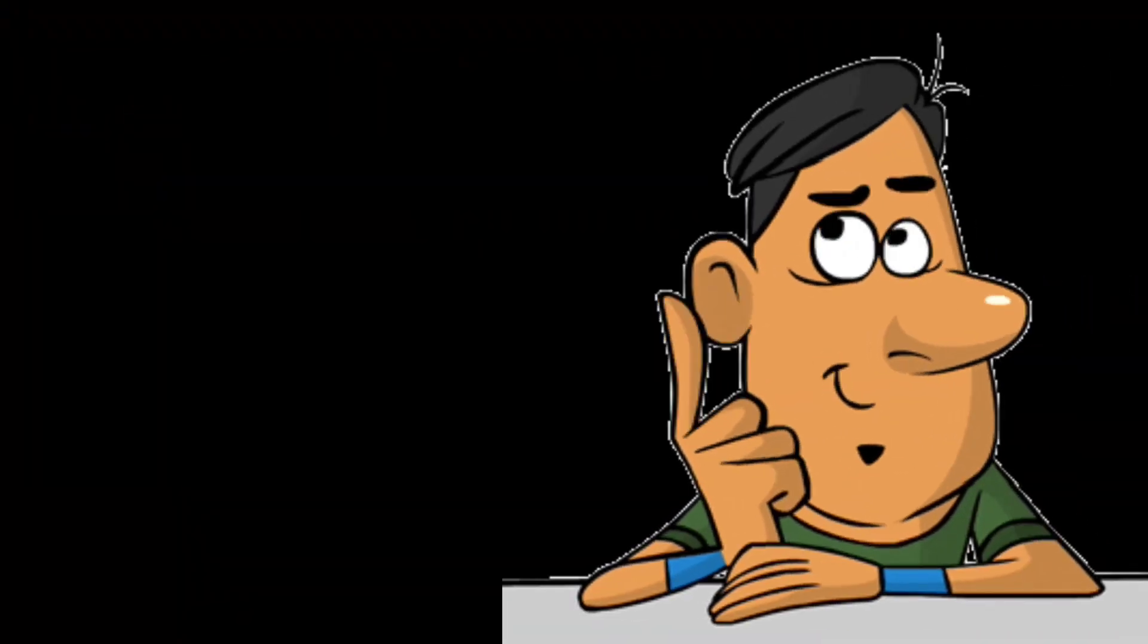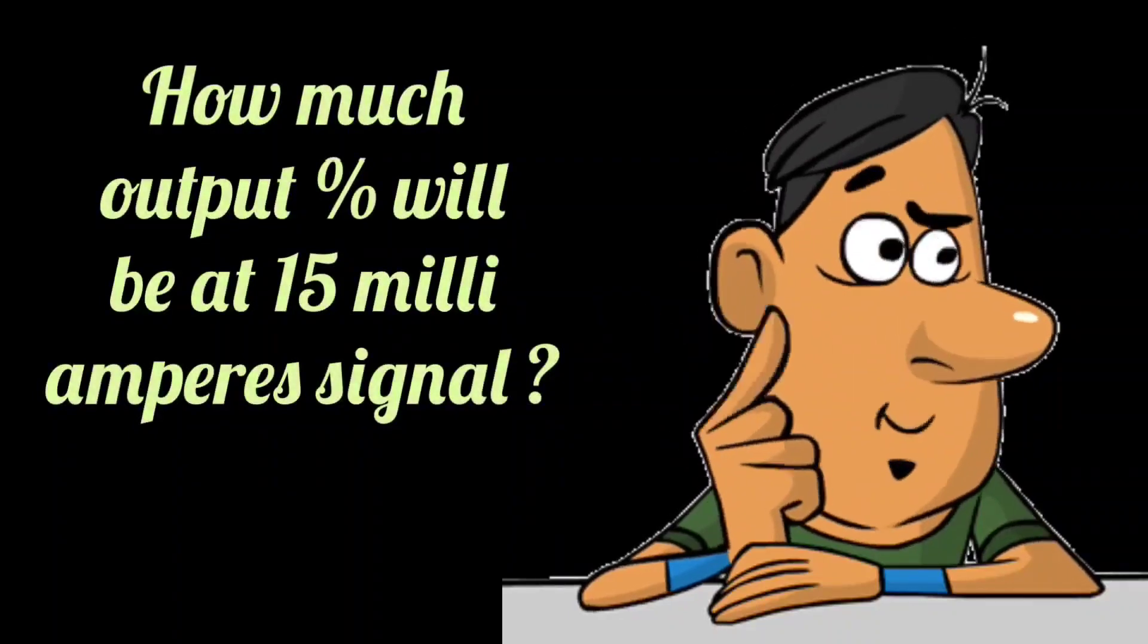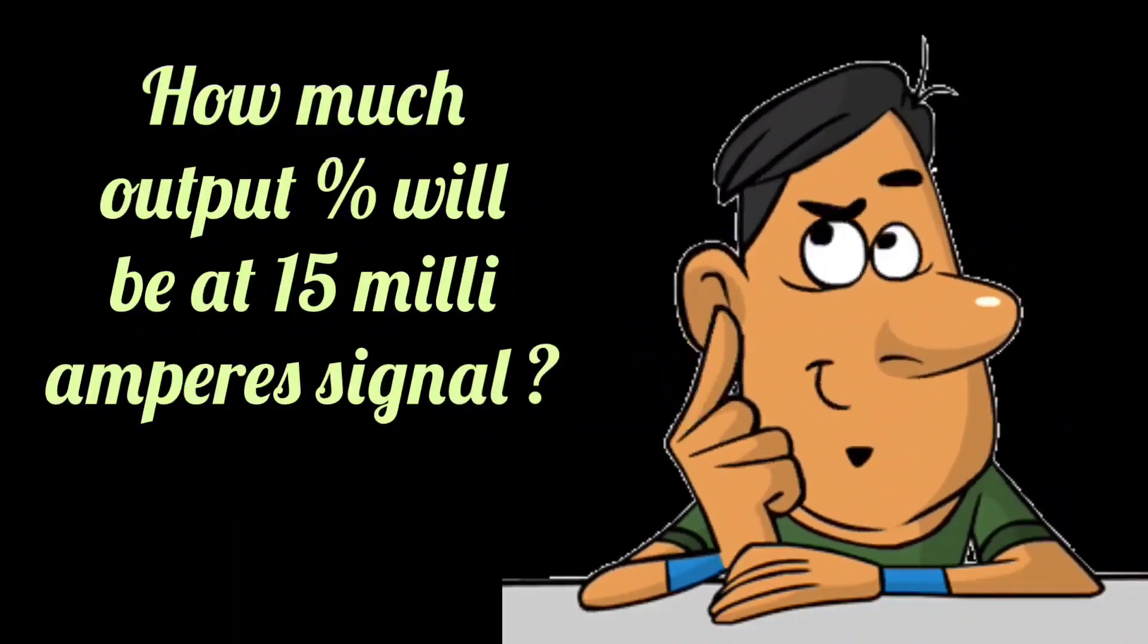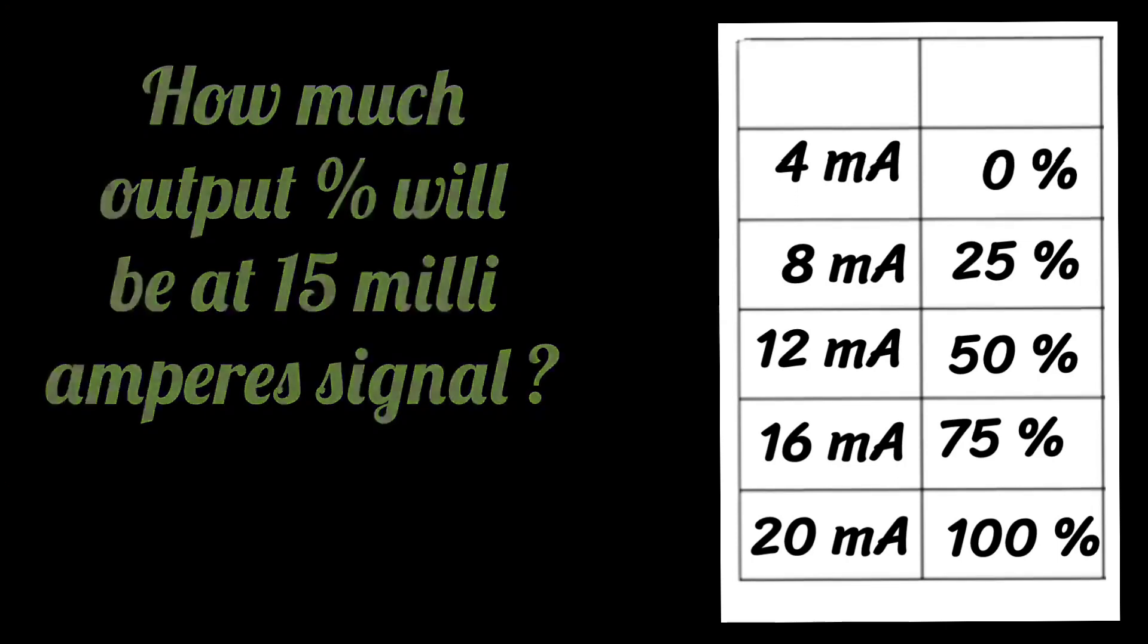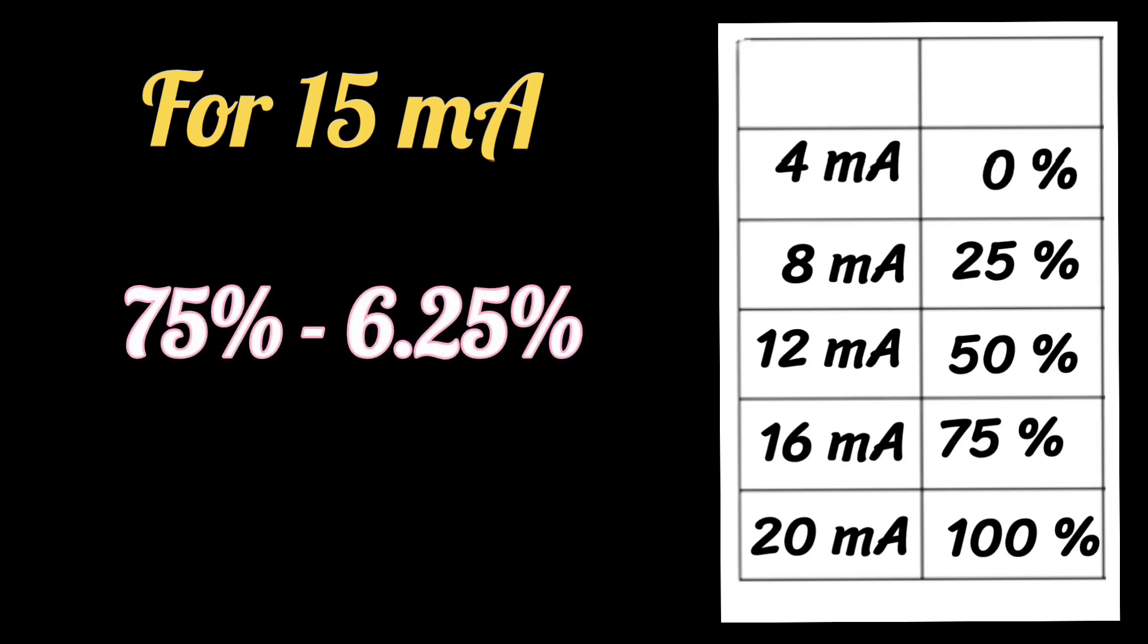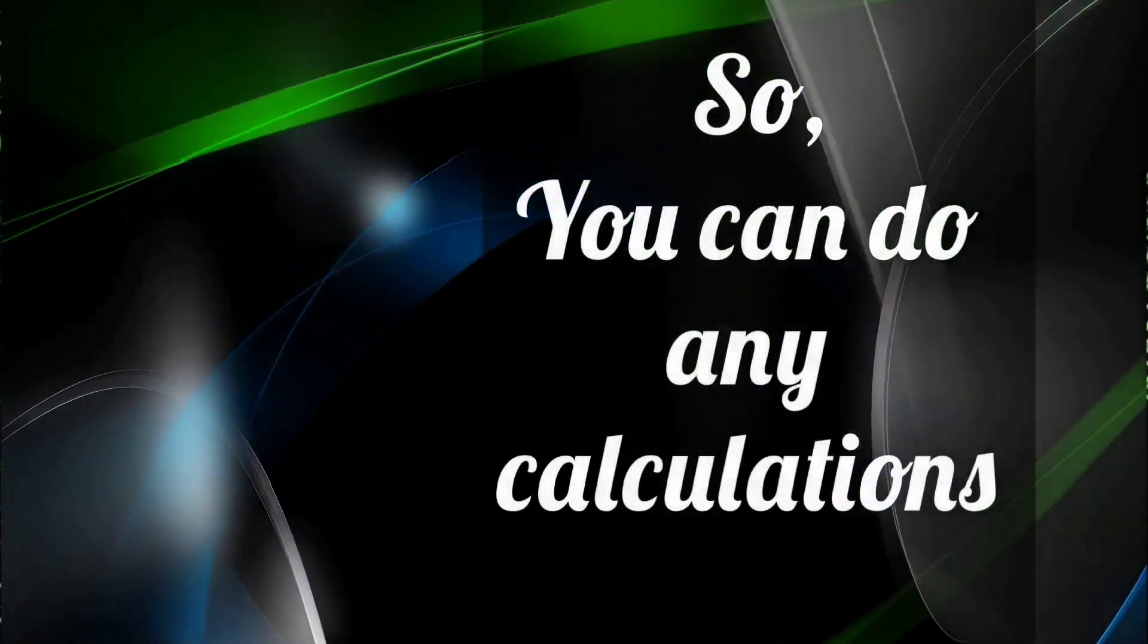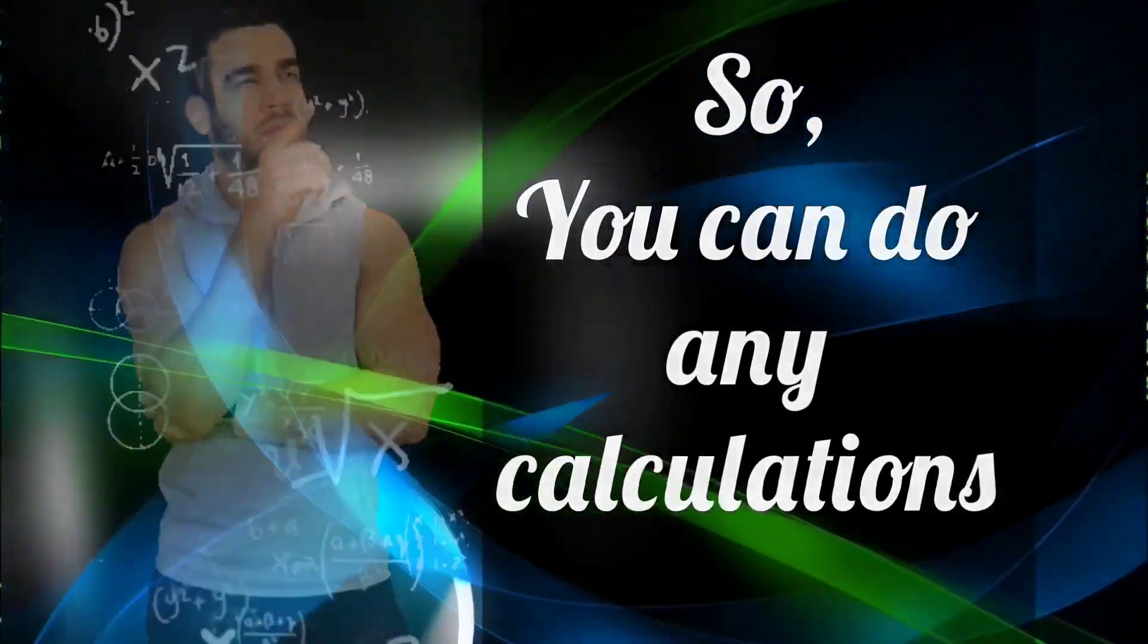If you have to tell what will be the percentage output at 15 milliamperes, you can easily tell this because at 16 milliamperes, 75% is the output signal. For 15 milliamperes, subtract 6.25% from 75%, and you will get the answer. So you can do any calculations, it is very easy to understand.